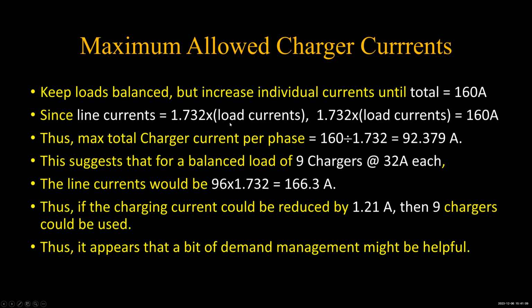So, charger currents, loads balanced. This is the bottom line of what we just did. If we went up to 9 chargers, we have 166.3 amps. That's 6.3 amps too much. So what if we reduce the charging current by 1.21 amps? Then you could use 9 chargers.